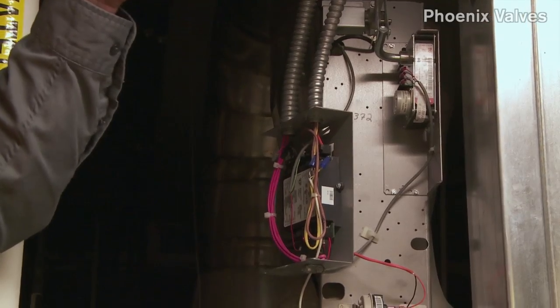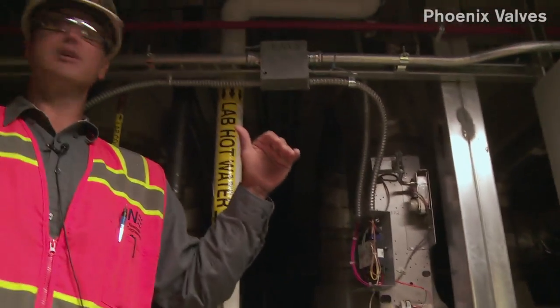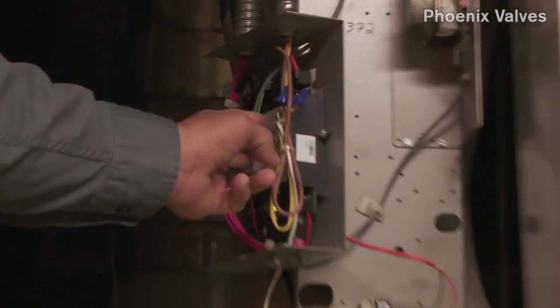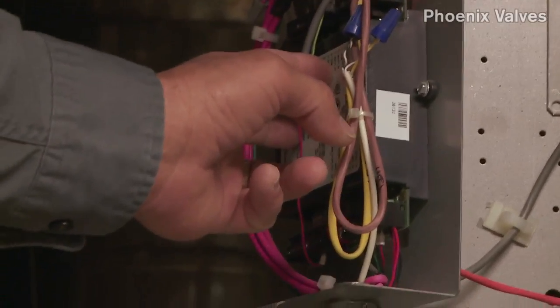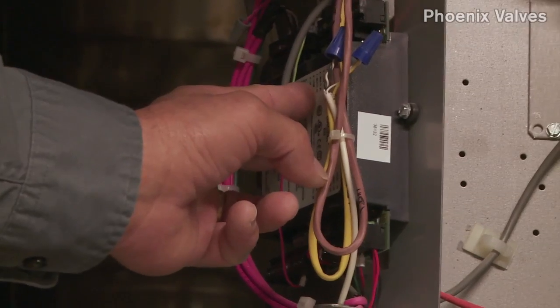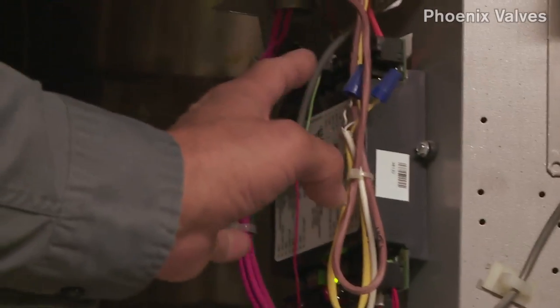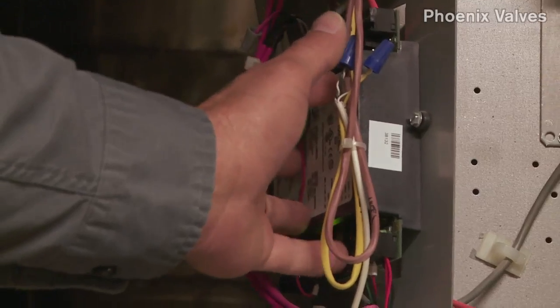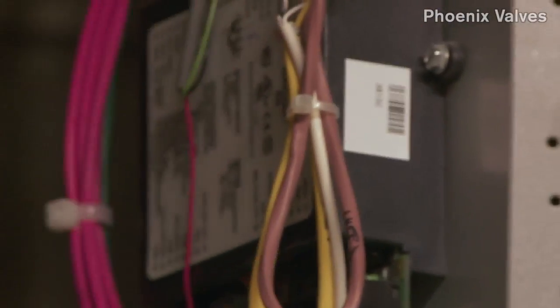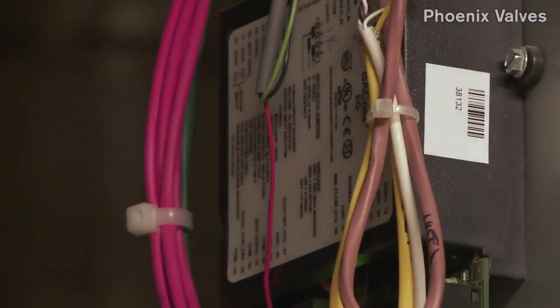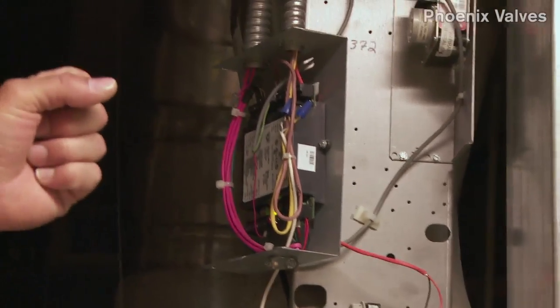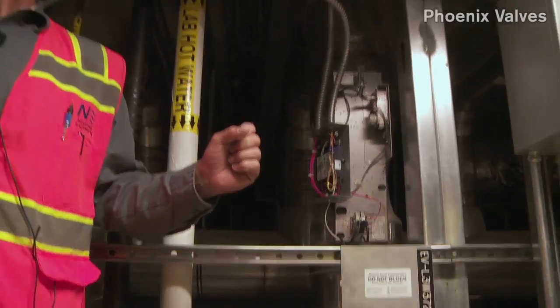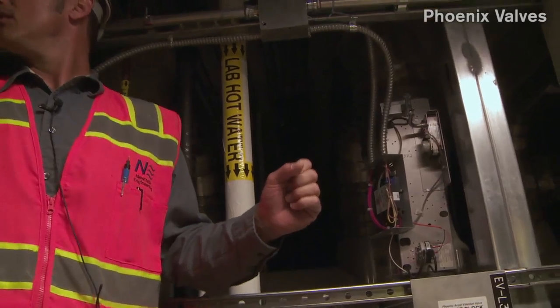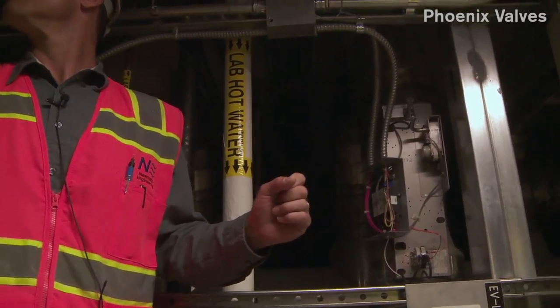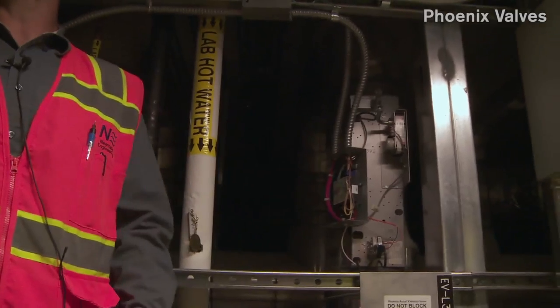When there's a fume hood landed on it, like the ones where the fume hoods are, our pressure switch has to be landed on this board. We'll get the alarm coming through here. Actually, it doesn't really need to be landed to the board unless we're talking to your front end and we're supplying all of your front end system. But I think in this building we still have the pressure switches going directly to JCI, right? Right. The difference is, on a fume hood, the pressure switch goes directly to the monitor, and from the monitor we have direct contact. So a fume hood application is slightly different.